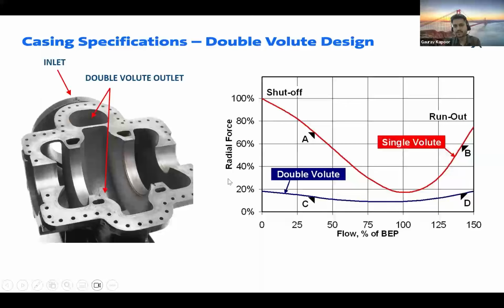On the y-axis we have radial forces, and on the x-axis we have flow percentage of BEP. Now what is BEP, we will understand. So let's imagine this point is the BEP. BEP stands for best efficiency point. So any centrifugal machine will have a point where it delivers the best efficiency. It means it consumes the lowest kilowatts to deliver you the maximum output.